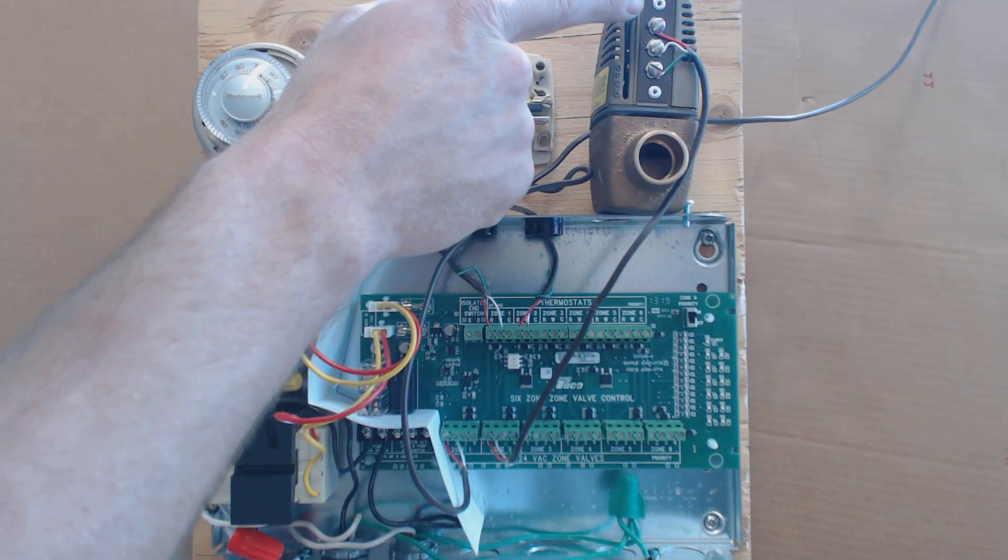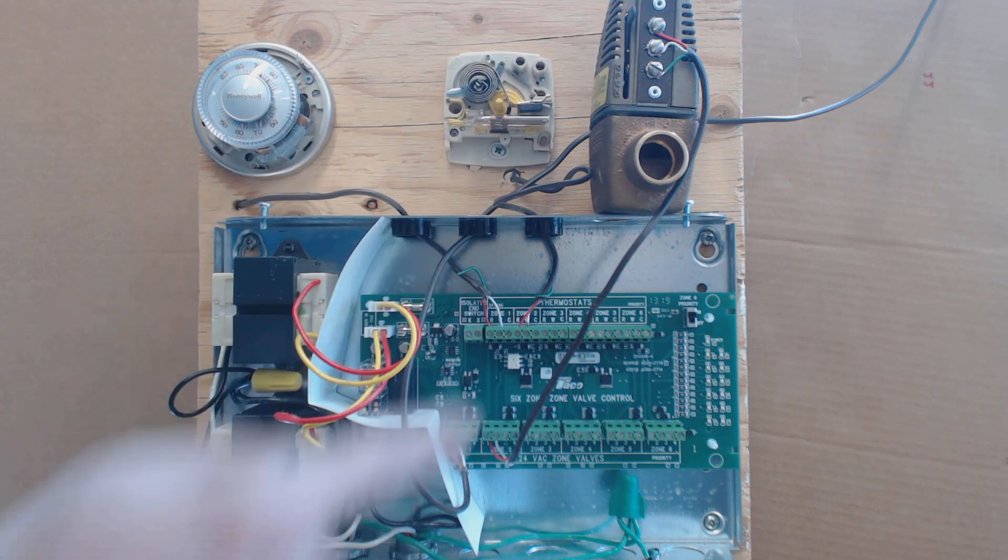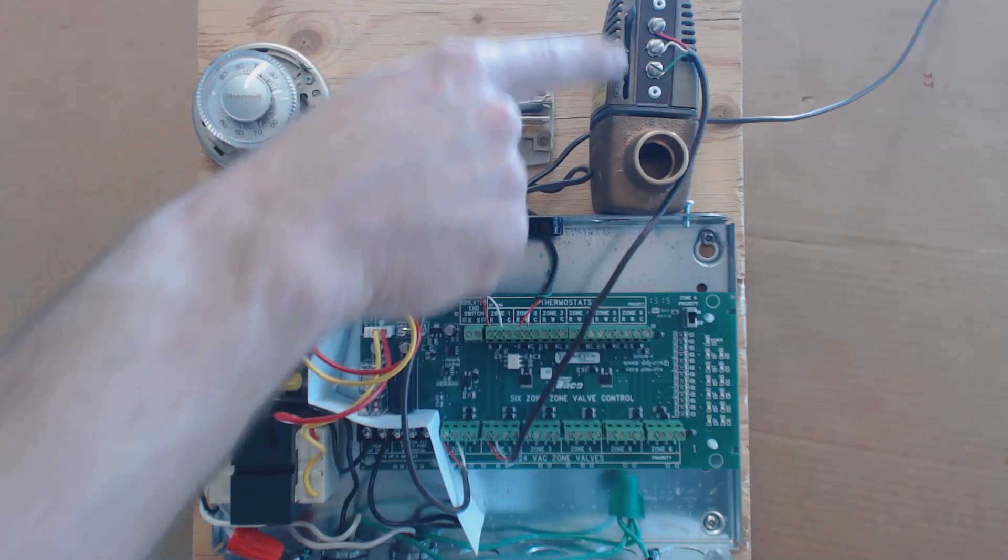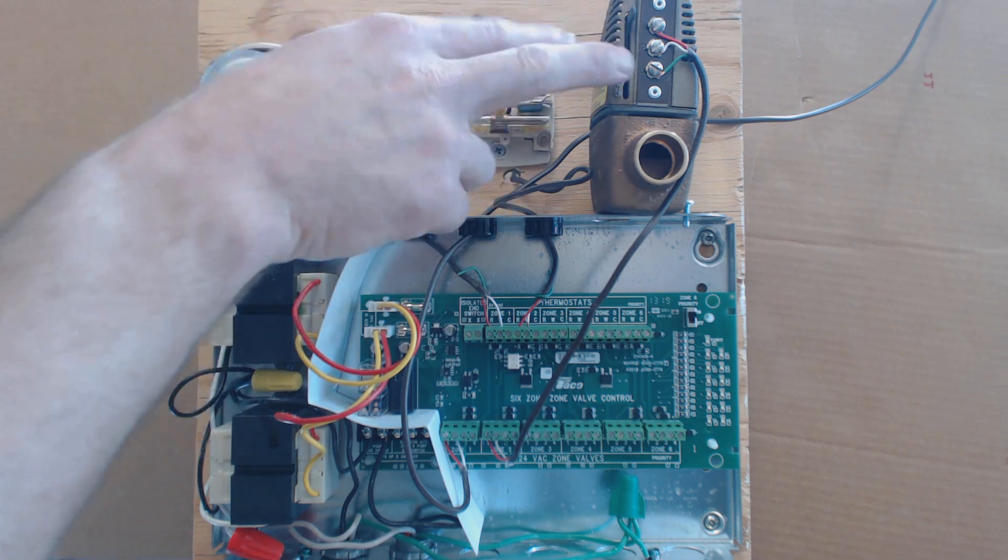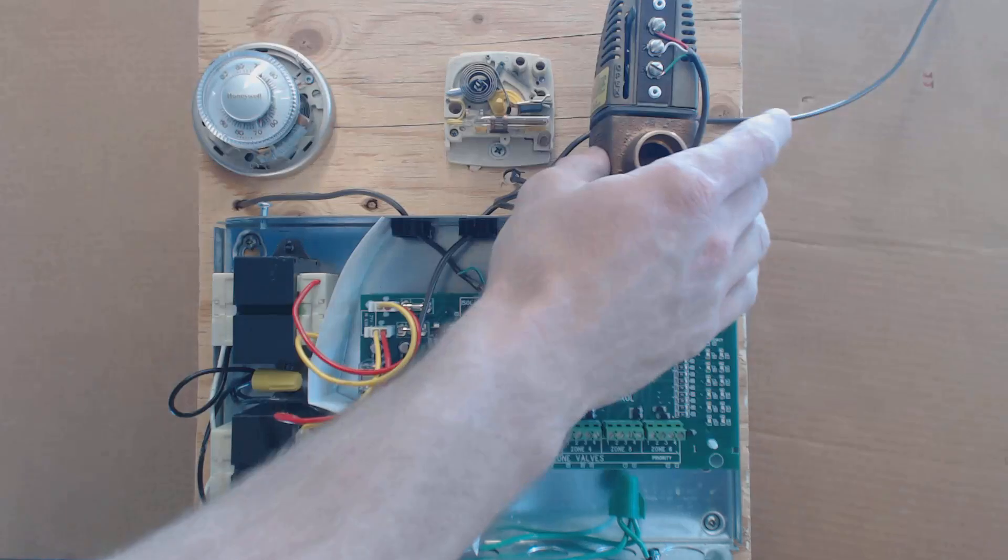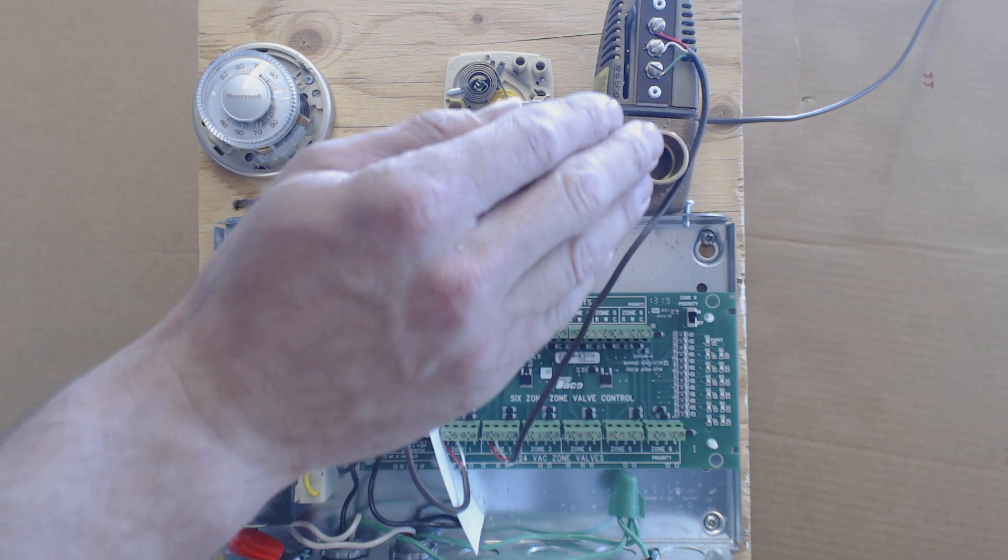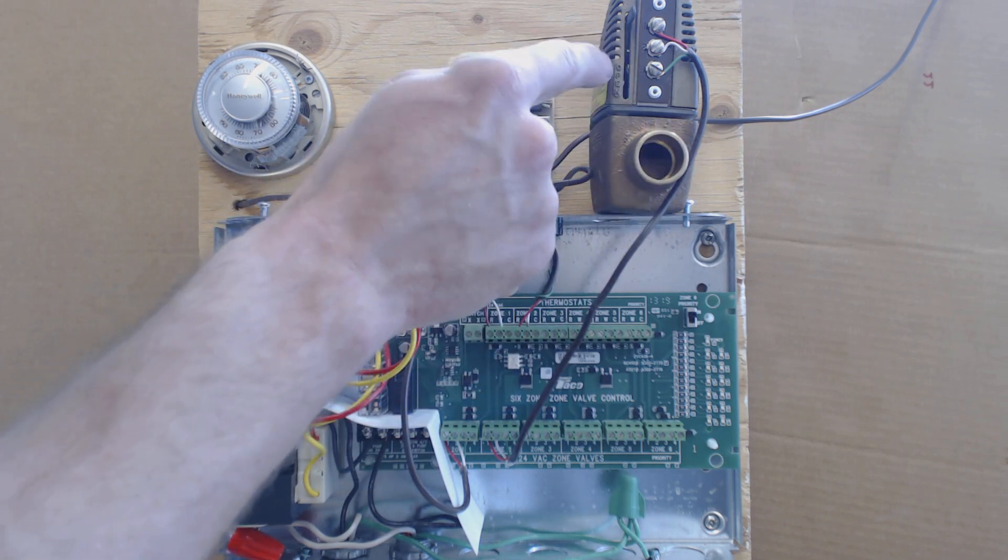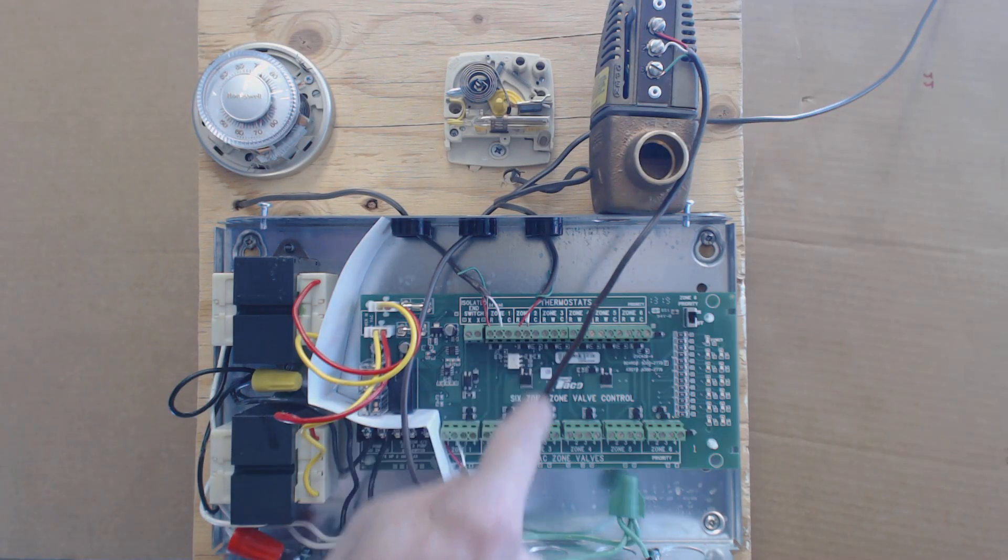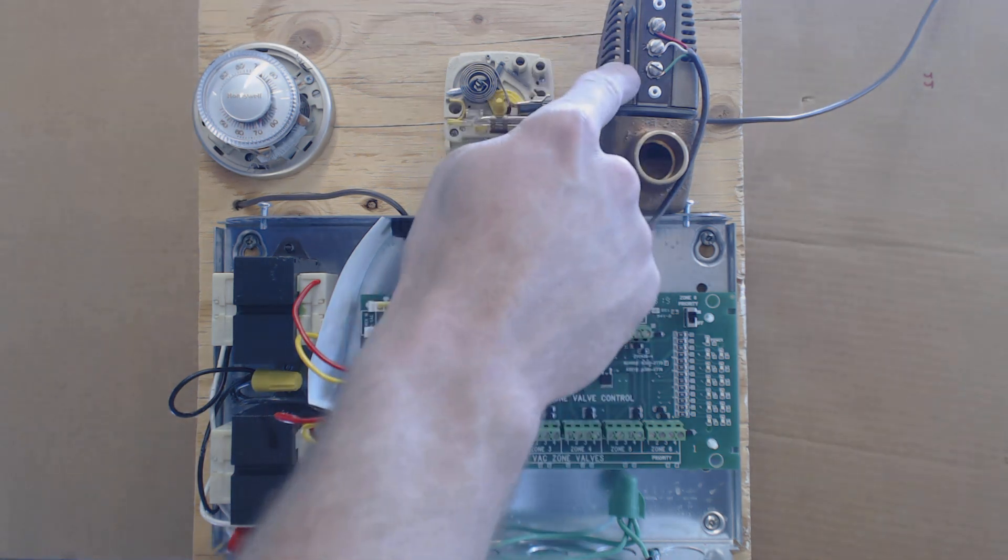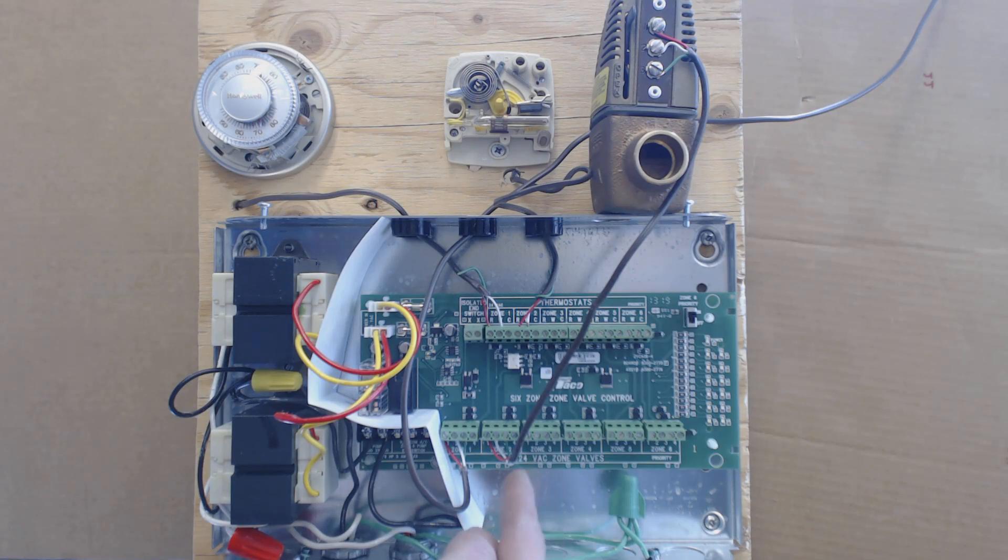What you have is one is the power coming in, two is the common, and three is an end switch. Once this heats up, you have 24 volts, the hot and the common, powers the heater in here, and that presses down on the valve body and allows the water to flow through. Once that happens completely and you have water that's actually able to flow through, then two and three connect via a switch inside the TACO head here. Once C gets continuity, your common gets continuity with number three, so number two gets continuity with number three, then that is when your circulating pump turns on.